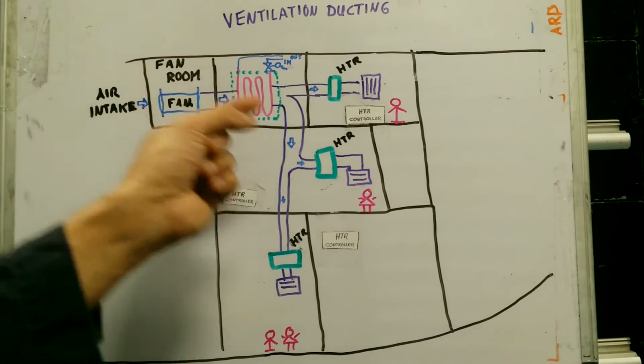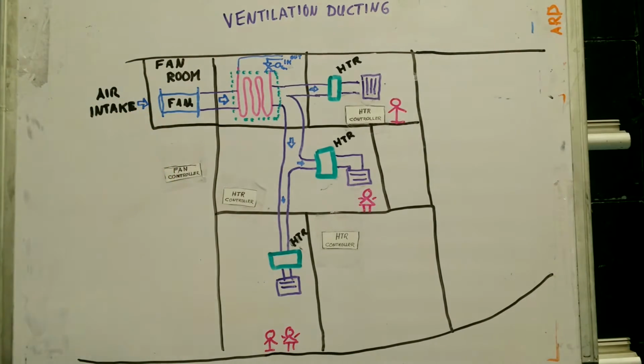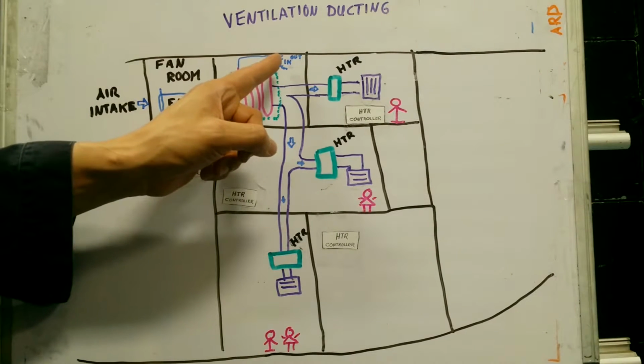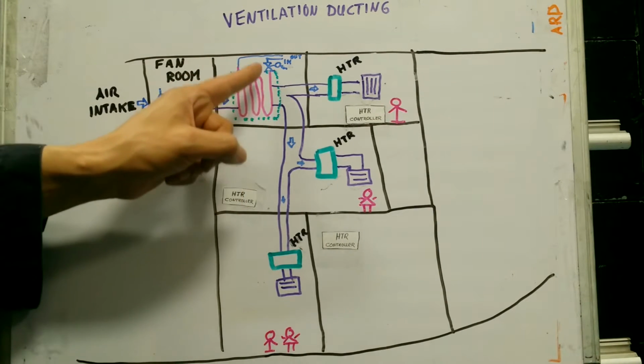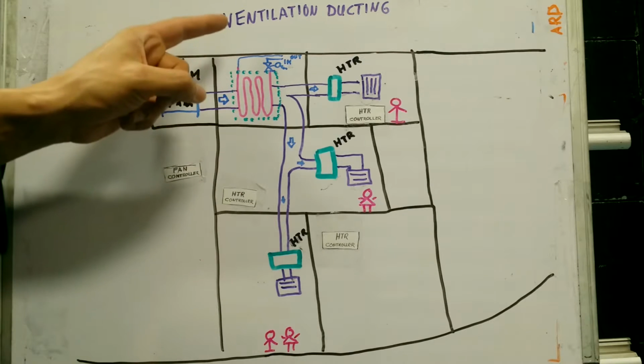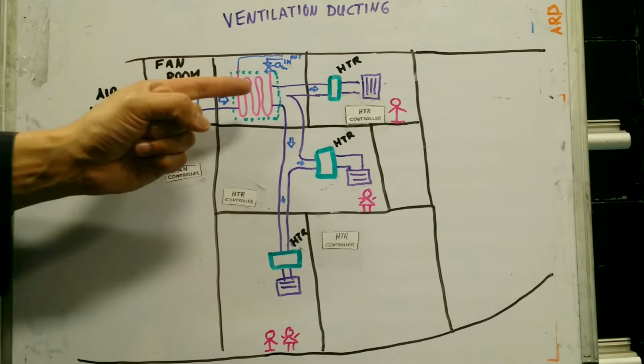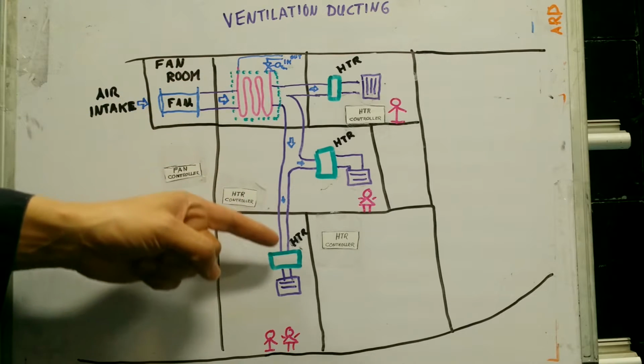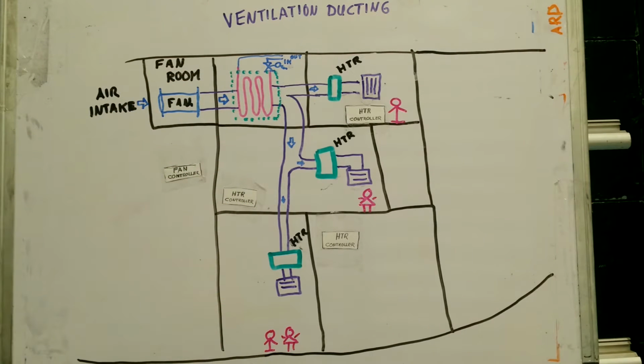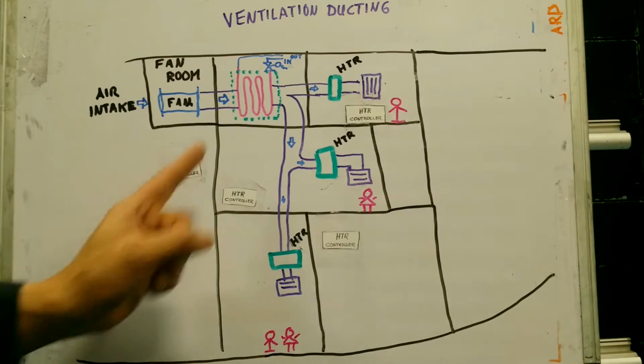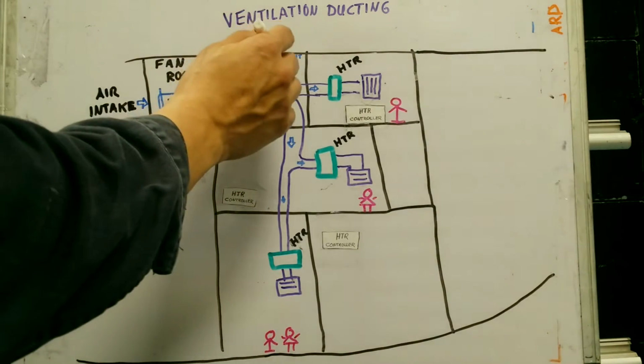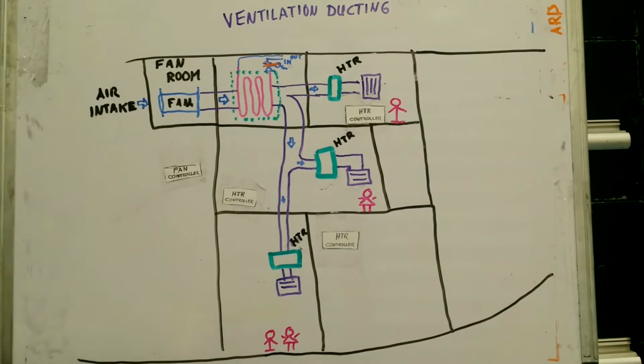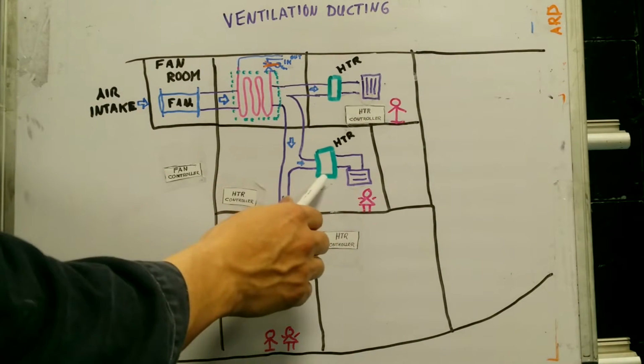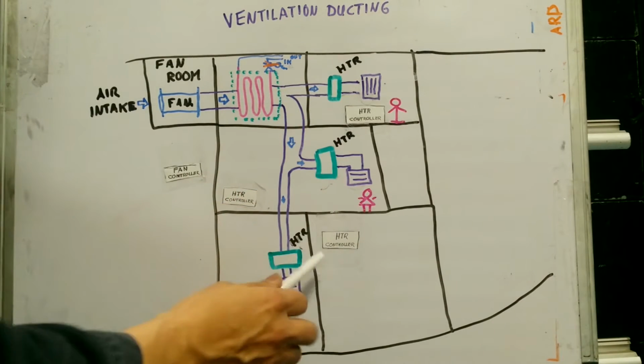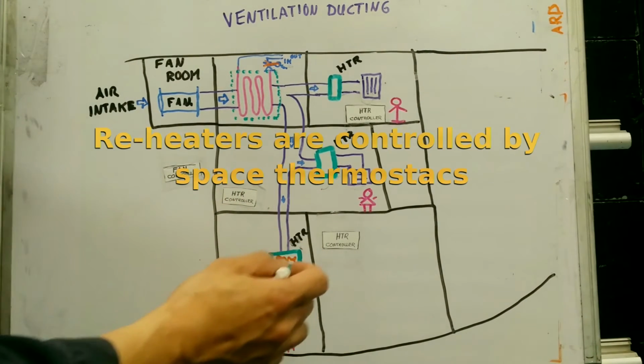Now, let's say that it is a hot day. What's supposed to happen is that a solenoid valve opens and allows chill water to go into this heat exchanger, and it will cool the air that passes by. Once the air continues, it will cool down the space down below. Now, what if it's winter and it's cold? We want the solenoid valve to stop the water flow, the chill water, and then they've got these heaters that come in and heat up the air, so as it comes out, the air comes out warmer.